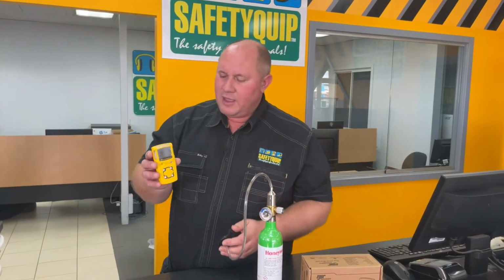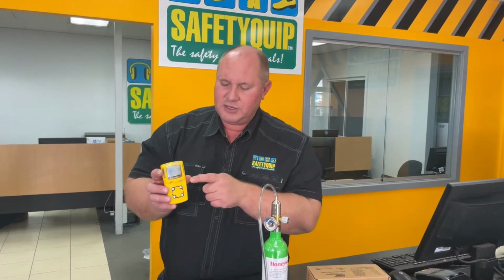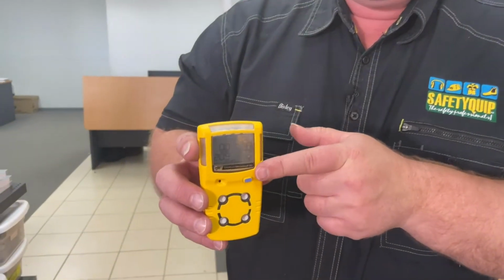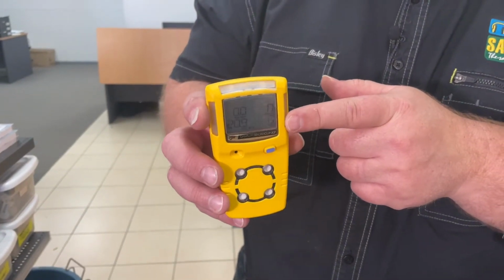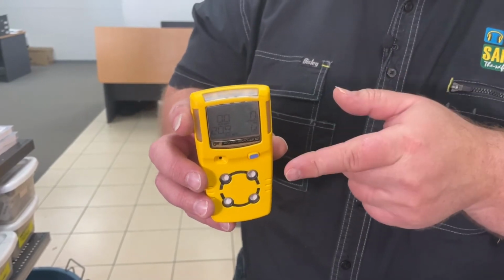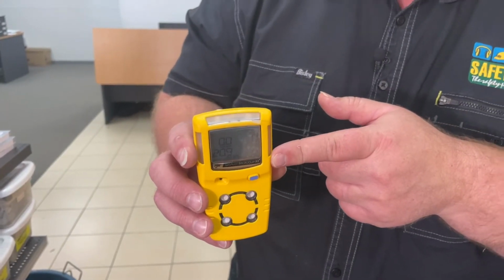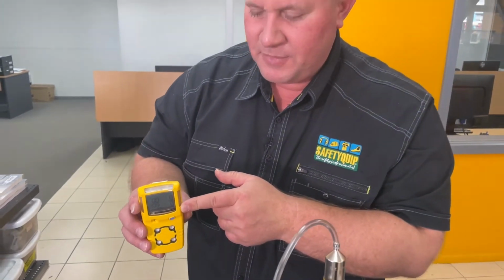So what I'm going to do in a moment is I'm going to press the only button that's on the front of the gas detector. That's normally the on-off button. So I'm going to press and hold it beyond it switching off. So it's going to turn off. I'm going to hold it a bit longer, and then it's going to initiate the calibration process. I'm going to let that count down, and then it'll start to calibrate.